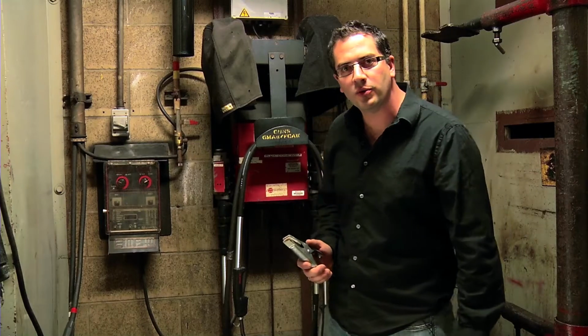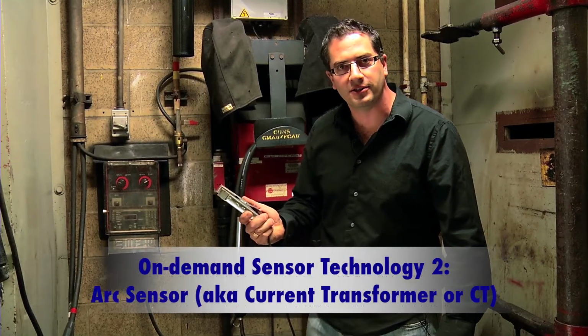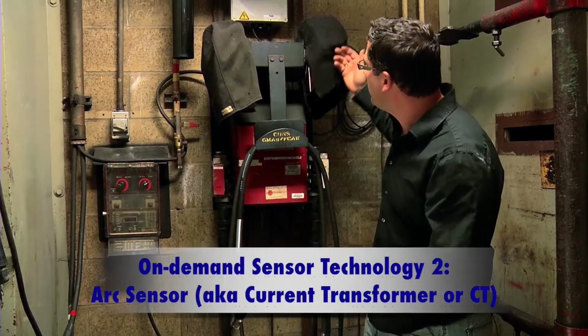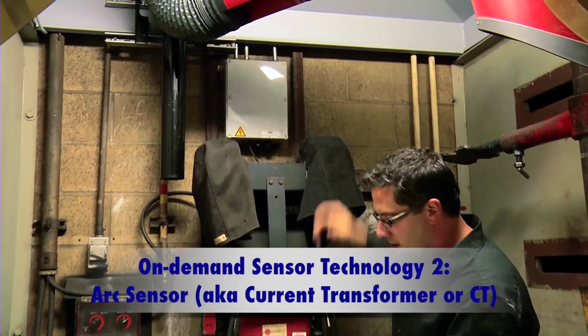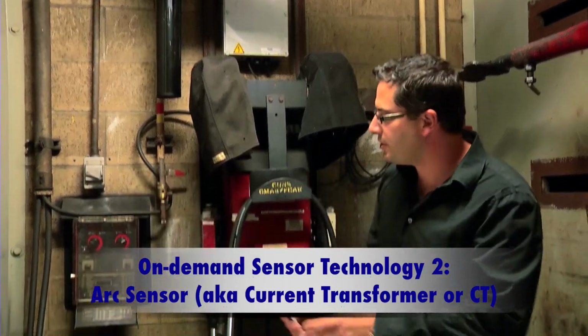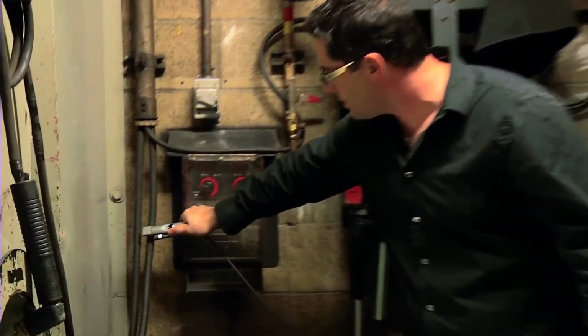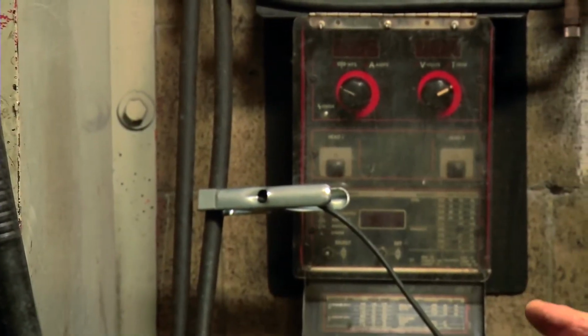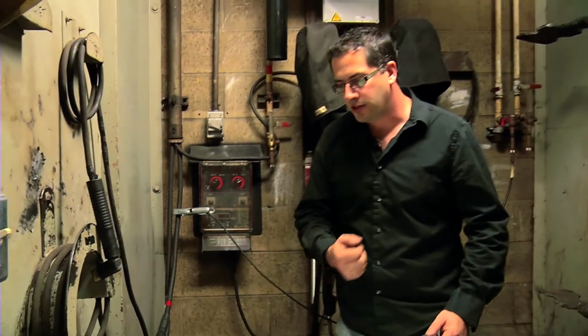Out of the 96 arc welding booths, 80 of them have an arc sensor. You'll see here that we have a control panel up here. It goes to a clamp that clamps onto the welding circuit. As we put it onto the welding cable, currently the system has an open circuit. Once you strike the arc and start welding, it's a closed circuit.